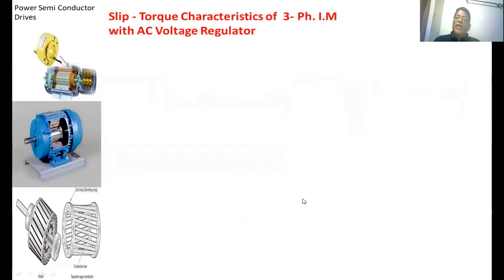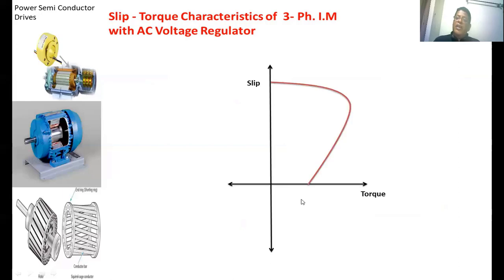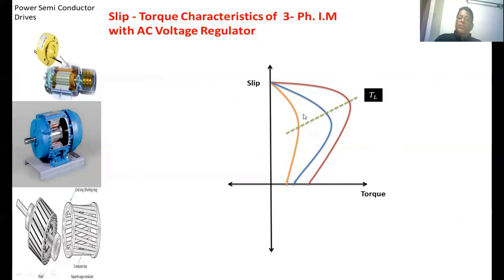Now we look at the slip-torque characteristics of a three phase induction motor with AC voltage control. On the x-axis we have torque and the y-axis we have slip. This shows the speed-torque characteristics for rated voltage, reduced voltage, and further reduced voltage. A load torque line intersects the three slip-torque characteristics at different points. As the voltage decreases, the slip of the induction motor increases, meaning the speed of the motor decreases. By applying variable voltage to the induction motor, the speed can be varied, but the rotor losses increase. This type of stator voltage control is suitable for domestic fans and pumps.